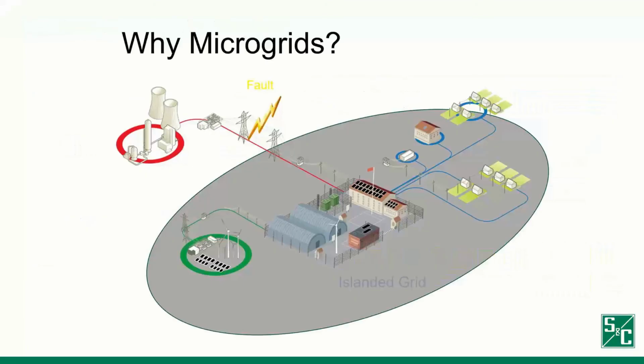But why do we need microgrids? Besides load centers, there are three distinct components in a microgrid, including switching equipment, controls, and DERs. Each of those offers advantages that can benefit the end user and improve the performance of the system. According to Microgrid Knowledge Group, the microgrid is defined with three key characteristics. It's local, meaning it creates energy for nearby customers. It's independent, meaning that it can disconnect from the central grid and operate in island mode. And it is also intelligent, which mainly refers to the application of the microgrid controller.